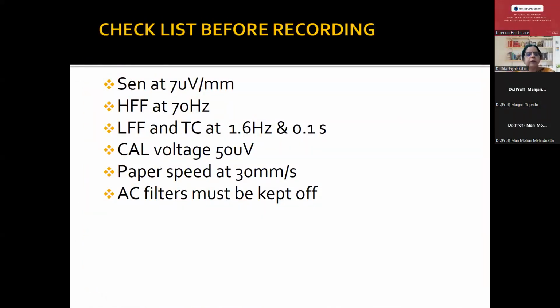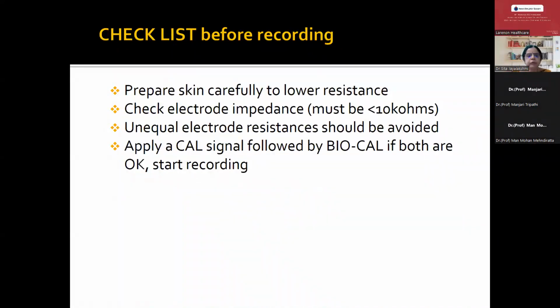So to summarize the recording, one should have the checklist before recording with a sensitivity of 7. Normally sensitivity is around 7, which can be adjusted, but most important are high frequency filter at 70 hertz, low frequency filter of 1.6 hertz, or the time constant of 0.1. Calibration voltage should be 50 microvolts, paper speed at 30 millimeters per second, and the AC filter should be always kept off. And one should make sure that the skin is prepared carefully to lower the resistance. One should check the electrode impedance, which should always be less than 10 kilo ohms. Unequal electrode resistance should be avoided.